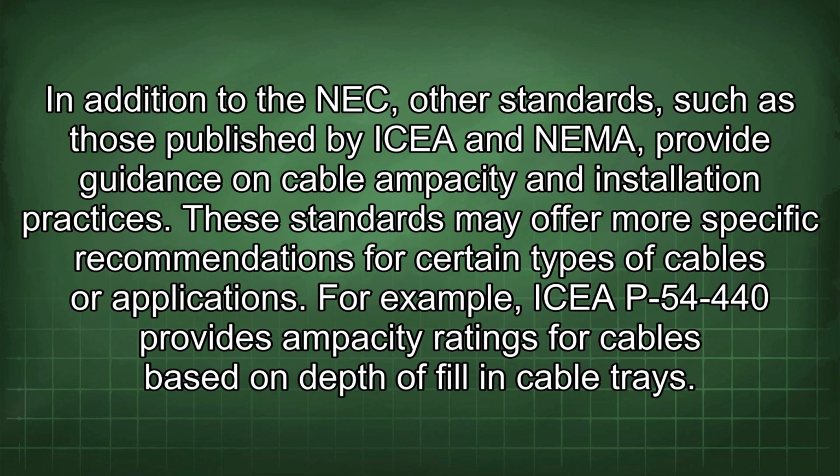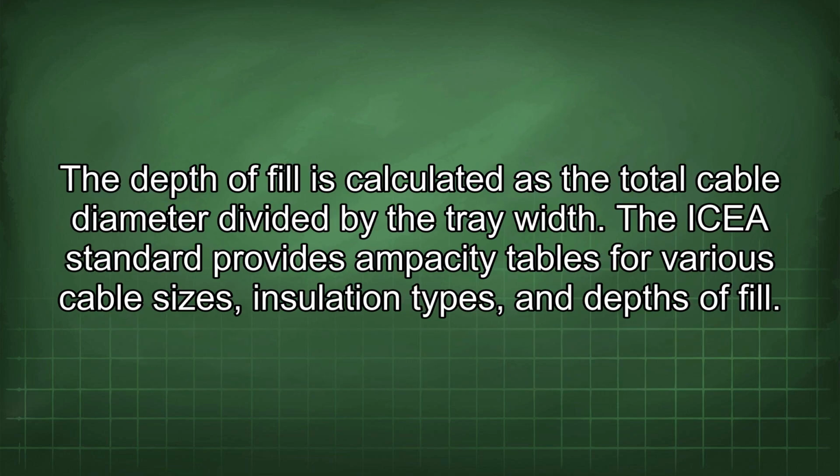In addition to the NEC, other standards, such as those published by ICEA and NEMA, provide guidance on cable ampacity and installation practices. These standards may offer more specific recommendations for certain types of cables or applications. For example, ICEA P-54-440 provides ampacity ratings for cables based on depth of fill in cable trays. The depth of fill is calculated as the total cable diameter divided by the tray width. The ICEA standard provides ampacity tables for various cable sizes, insulation types, and depths of fill.